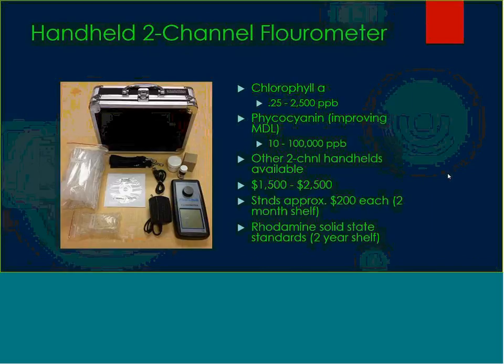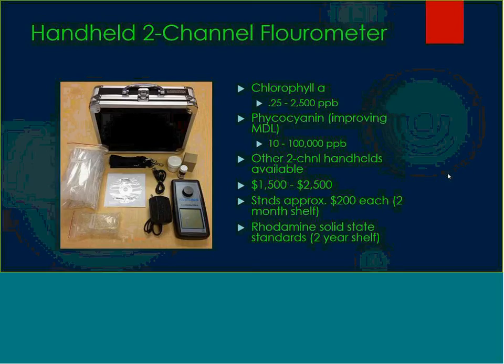The tool we use for looking at fluorescence is a handheld field fluorometer — there are several types available. The measurement range for chlorophyll is from 0.25 to 2,500 micrograms per liter, and the phycocyanin is 10 to 100,000. We're working on trying to bring that minimum detection level down a little bit for the phycocyanin. They range anywhere from $1,500 to $2,500 depending on brand. Standards are approximately $200 a piece for calibrating with a two-month shelf life, and calibrations are usually good for a year or better. You can get rhodamine solid-state standards to track instrument drift through the course of your sampling period.